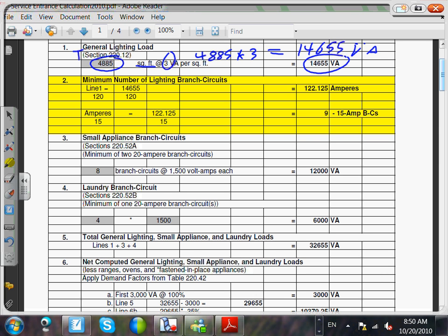And now when we go to the common area, there's a common panel or house panel. When we go to the house panel, listen to me carefully, take the area of the common areas: stairways, hallways, common stairways, utility room, what else? Common between them. That's it. Stairways, hallways, and utility room, which is common between all of them. And you put the square foot of this common panel here, and you do the same calculation.